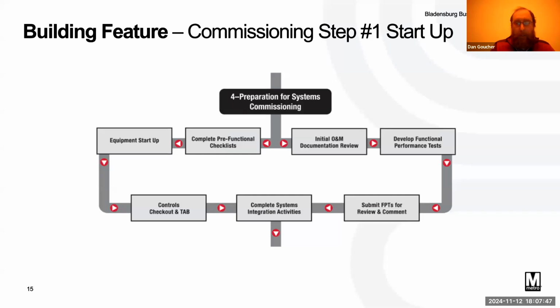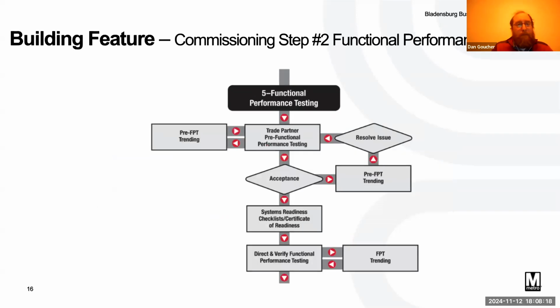Within startup, we're also doing pre-functional checks, making sure all of the wiring and piping is there - just some pre-checks before we actually start it up. We also start to initiate the O&Ms and look at different FPT, or functional performance test, procedures once we get into the next step. Next slide.